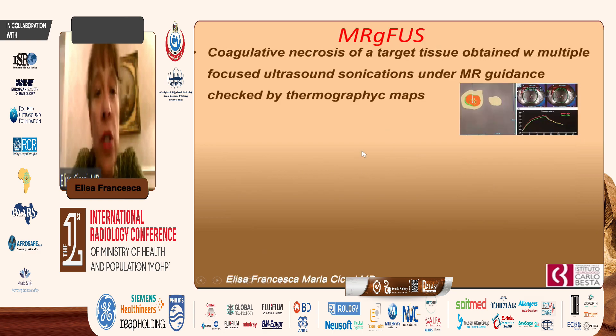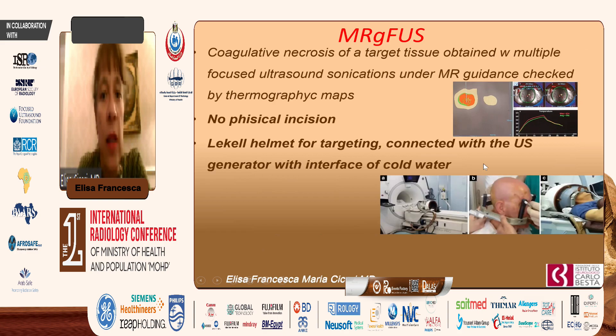MRgFUS can produce coagulative necrosis of a target tissue, obtained with multiple focused ultrasound sonications under MR guidance, checked by thermographic maps as you see on your screen. There is no physical incision, which is something very interesting for treatment on the skull. The Leksell helmet, as you see in the picture, should be put on the skull of the patient for targeting purposes, and then connected with the ultrasound generator via an interface of cold water behind a silicon membrane.